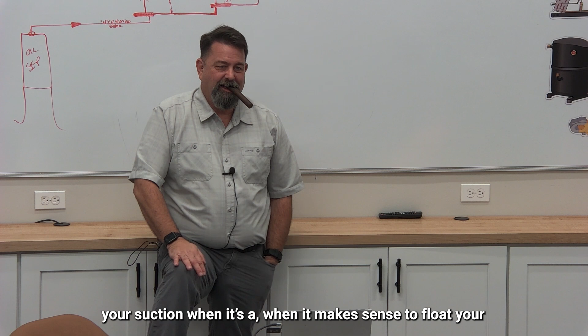10 PSI, right? I'm gonna let that pull down to 6, I'm gonna let that go up to 12, okay? That's kind of a normal swing. When I float, I'm gonna allow that to go up to 15, maybe 16, no higher, right? So I'm gonna spend a lot of time at 13, just a little higher than normal, right? That's traditionally what happens. Is it gonna cycle more? Yes, actually it will, right? There's no way it's not going to. It's not a huge amount, but it will cycle more, okay? Which kind of defeats the purpose and is one of the reasons why everybody's walking away from it, right?